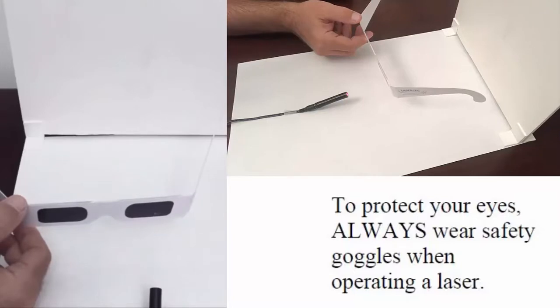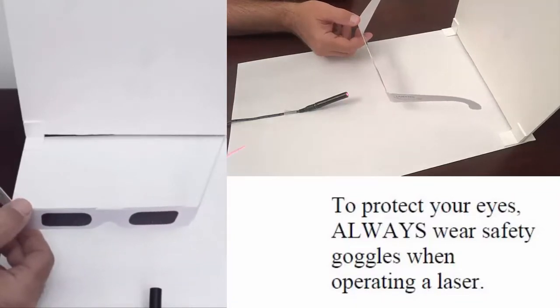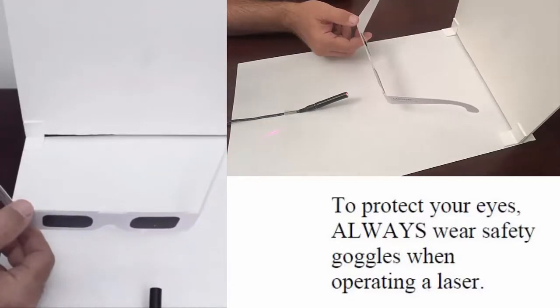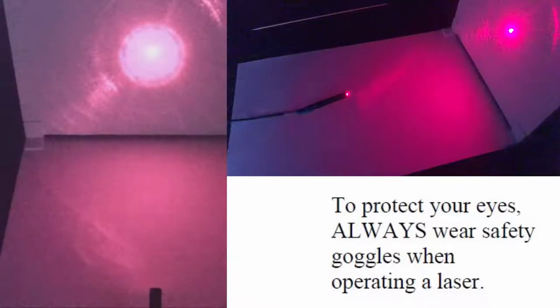To further demonstrate this effect, we are going to dim the light in the room, and we are going to use our spray to actually see the laser beam light traveling through the air and then being blocked by the laser safety goggles. As you can see, we have dimmed the light in the room. We can very clearly see our laser source right now, and a lot of laser light being produced and reflected off the back screen. So I'm going to spray the area through which the laser beam propagates to clearly see it in the air. So here it is.